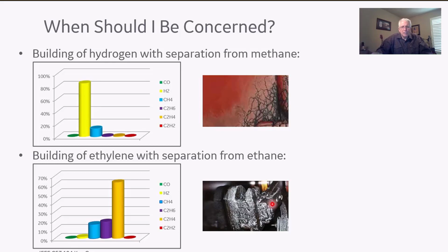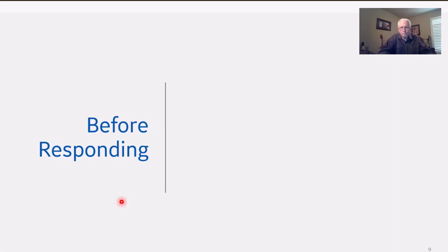So these days we begin to see a lot of overheating de-energized tap changers from earlier days of transformer building. So all the way through the 50s, 60s, 70s, 80s, that vintage of transformer. They've been on tap for so long now, you may start seeing this overheat. So as I look at the building of ethylene with some separation from ethane, you'll start seeing it actively generate, and you'll get some pretty good volume of ethylene. Once you do that, you can pretty much rest assured that your problem is visible. So if you roll somebody to go locate this problem, there's a very good chance they're going to find it and see it with their eyeballs, which is kind of important.